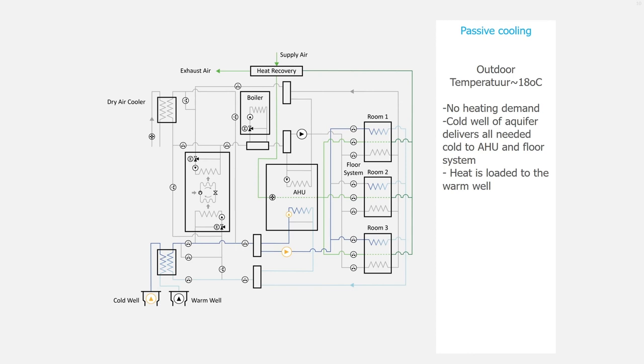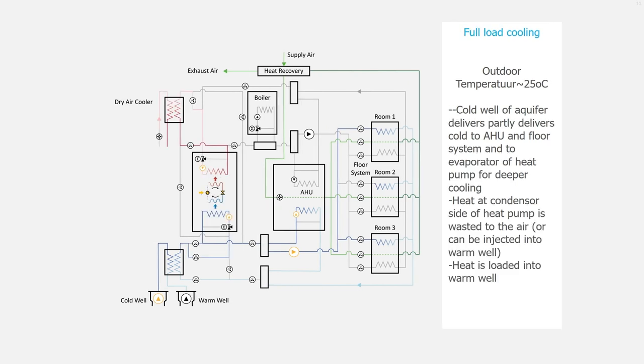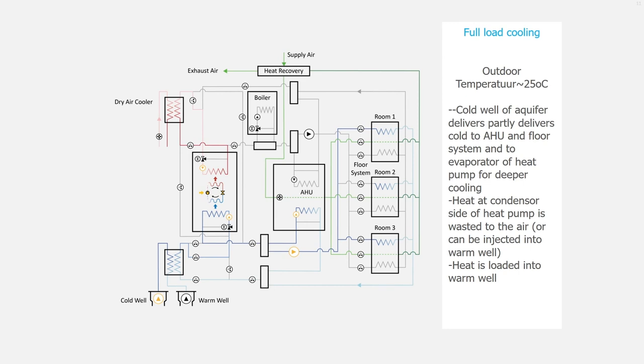Let's look now at full load cooling. The outdoor temperature will be around 25 degrees Celsius. The cold well of the aquifer delivers partly cold to the air handling unit and to the floor systems and to the evaporator of the heat pump for deeper cooling.